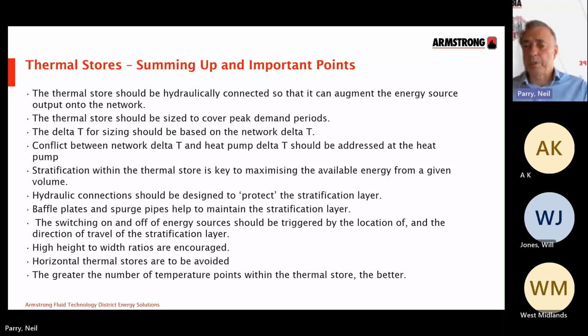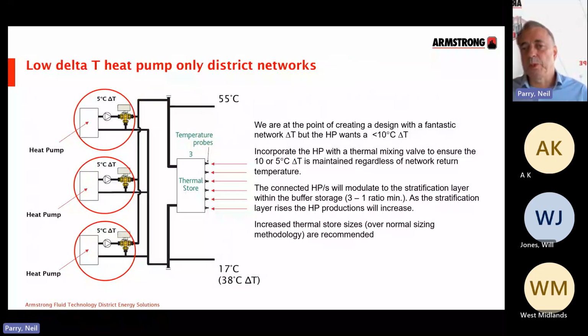So if we're looking at heat pump networks, what I would definitely recommend is having a 3-port valve arrangement around the energy source. We don't want to compromise the delta T on the network side. So you can see here, I've done a 55 flow with a 17 return, 38-degree delta T, with obviously an optimized network. And that 38-degree delta T would not be acceptable to the heat pump. So by having a 3-port valve arrangement around the individual heat pumps, we can now mix the flow into the return and have a microclimate where we're holding a specific delta T just around that heat pump. So it's happy with its 5 degree, and we haven't compromised the delta T on the network side.